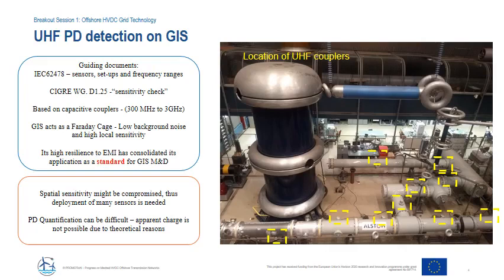To present, the UHF methods are the standard for AC GIS and are being migrated to DC GIS installations. They have indeed gained popularity because of their high local sensitivity and noise rejection. However, the PD signals in the UHF range are heavily attenuated with distance, requiring UHF couplers to be installed every few meters. The intrinsic nature of the UHF detection and the attenuation also make it impossible to quantify PD parameters, such as the apparent charge. TU Delft, in Work Package 15, has been researching complementary PD detection techniques that can mitigate the limitations of the reduced spatial sensitivity and PD parameter quantification of the traditional UHF methods.